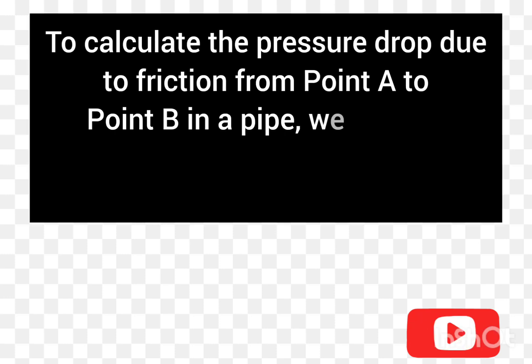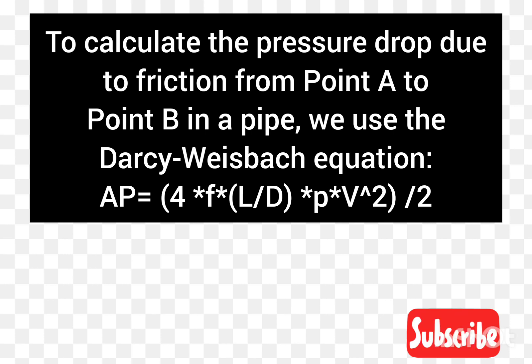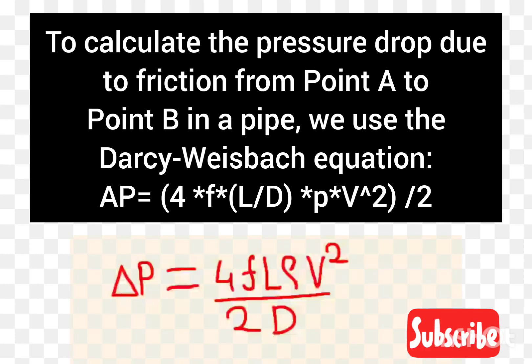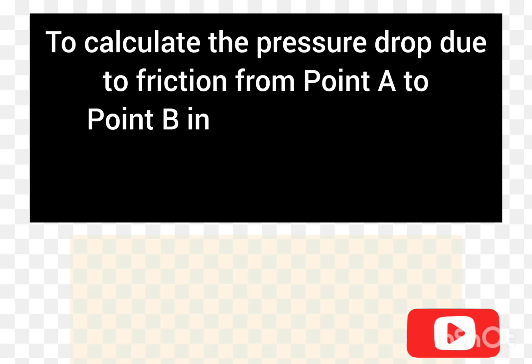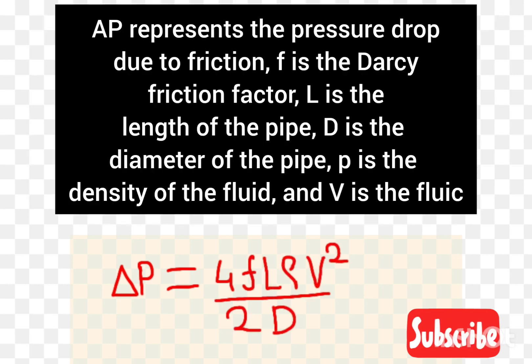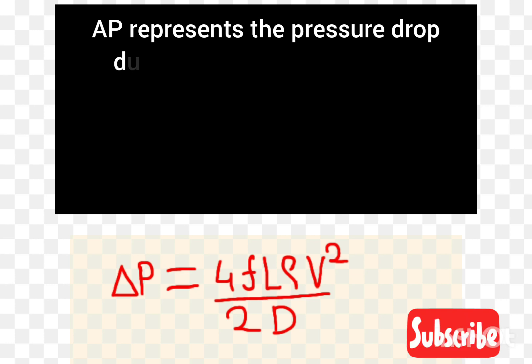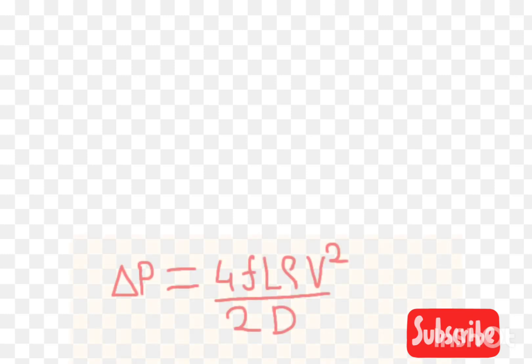To calculate the pressure drop due to friction from point A to point B in a pipe, we use the Darcy equation. The Darcy equation is: Delta P equals 4 times F times L times density times velocity squared, divided by 2D. Where Delta P is the pressure drop due to friction, F is the Darcy friction factor, L is the length of pipe, D is the diameter of pipe, rho is the density of the fluid, and V is the fluid velocity.